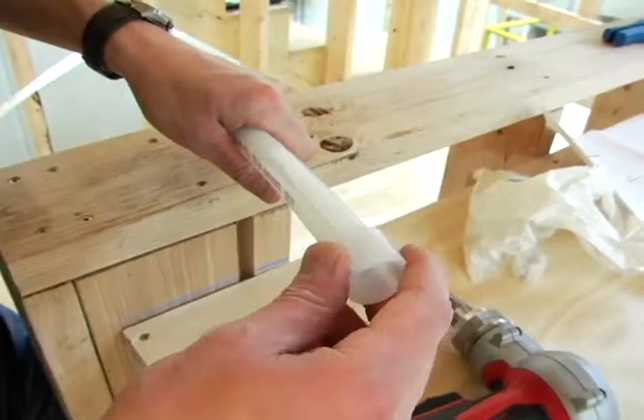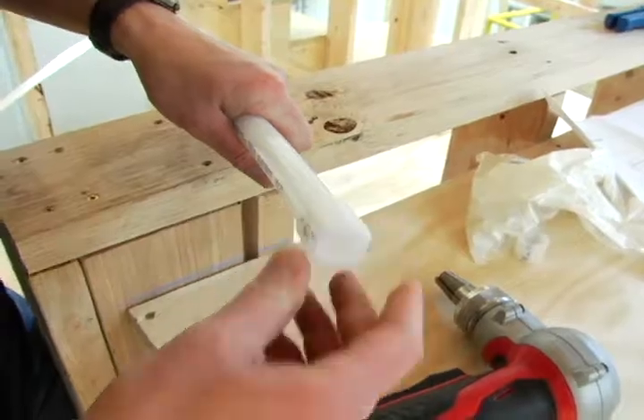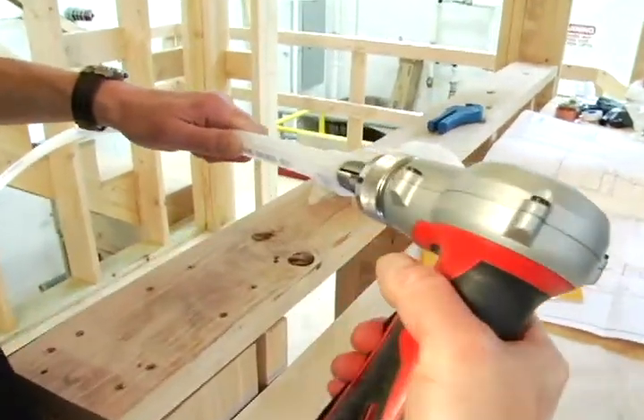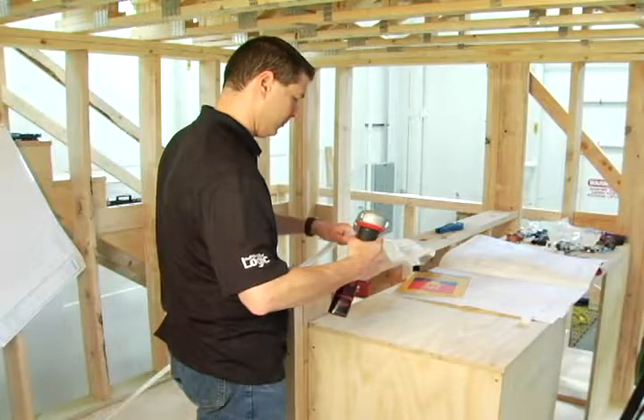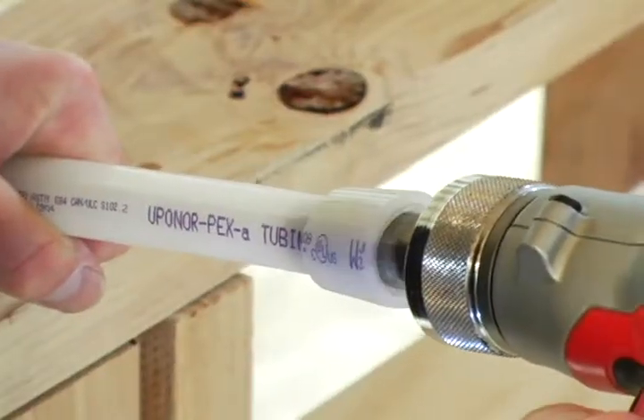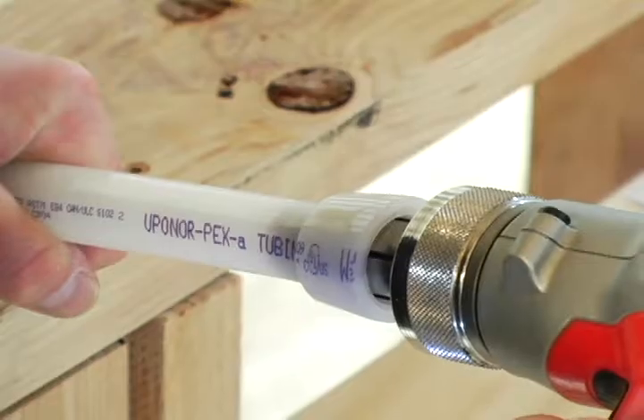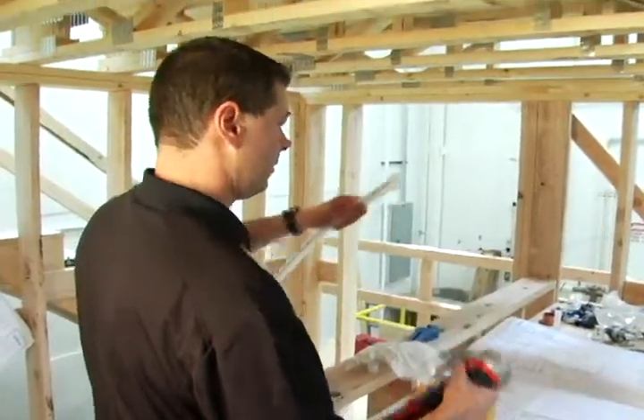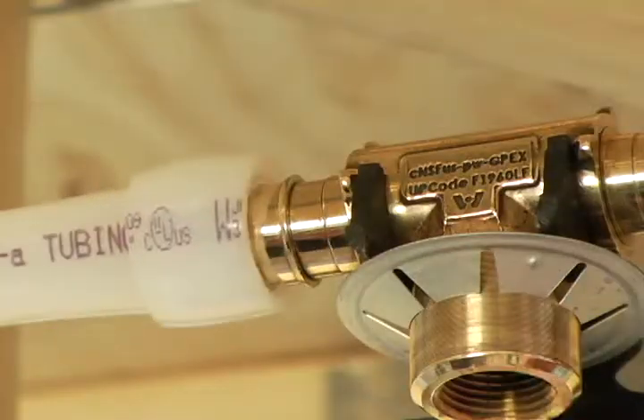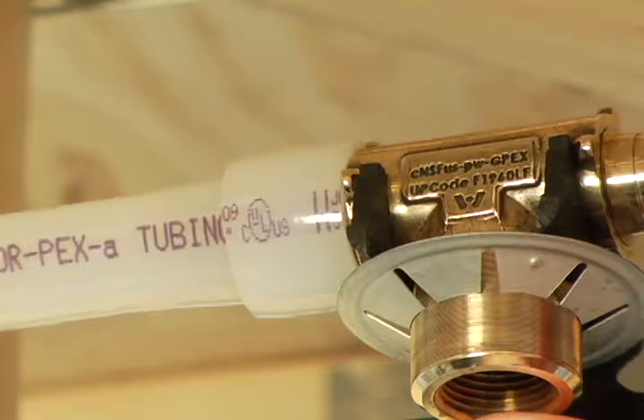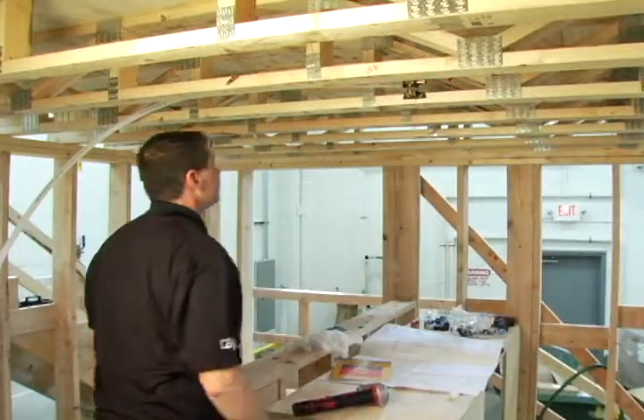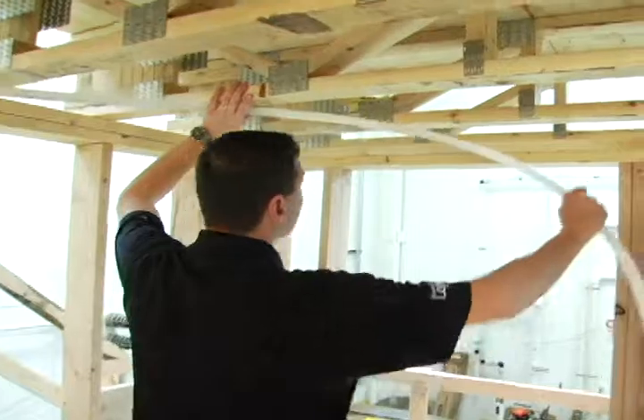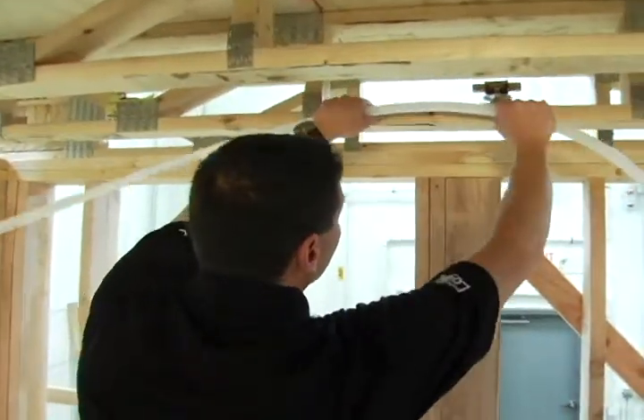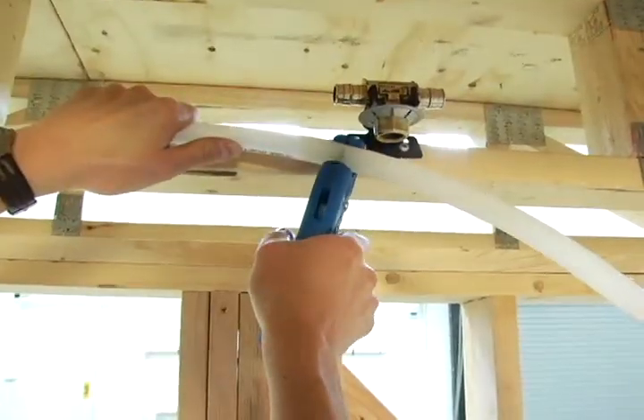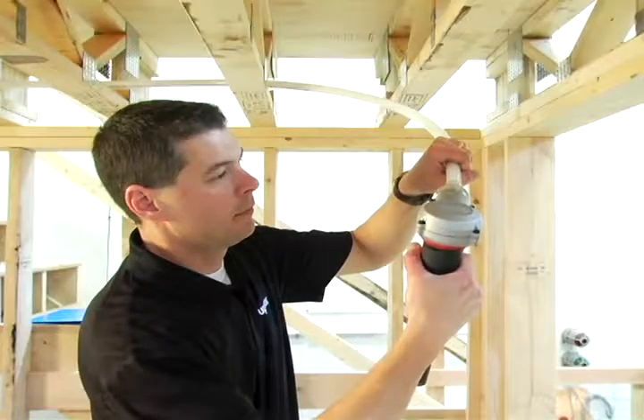To connect AquaPEX tubing to the sprinkler adapter, simply slide a Propex ring over the end of the tubing and expand both the tubing and ring with the Propex expander tool. When the tubing is fully expanded, insert the tubing over the sprinkler adapter fitting, ensuring it is fully seated. Within seconds, the tubing will contract around the fitting and the connection will be complete, and you can move on to the next fitting. Unroll enough tubing to reach the next fitting. Simply cut the tubing to length and repeat the connection process.